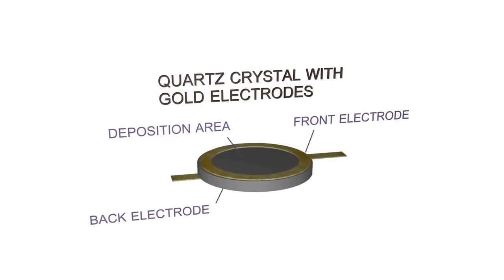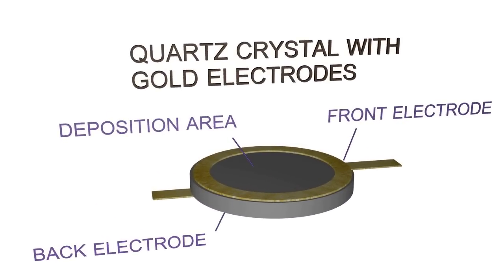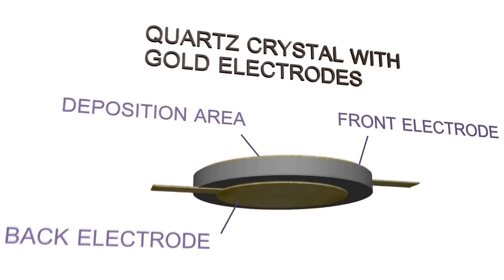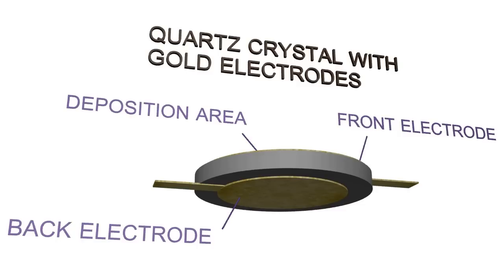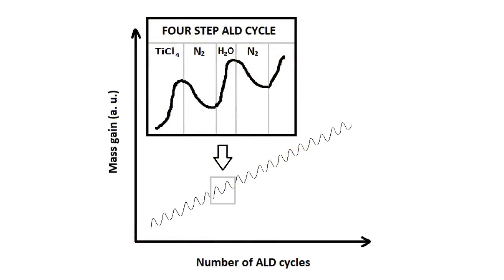The film growth can be monitored with the quartz crystal microbalance. If material is deposited on the quartz crystal during the ALD process, its mass slightly increases, causing a measurable drop in its oscillation frequency. This method is so sensitive that it allows monitoring even the individual steps in an atomic layer deposition cycle.